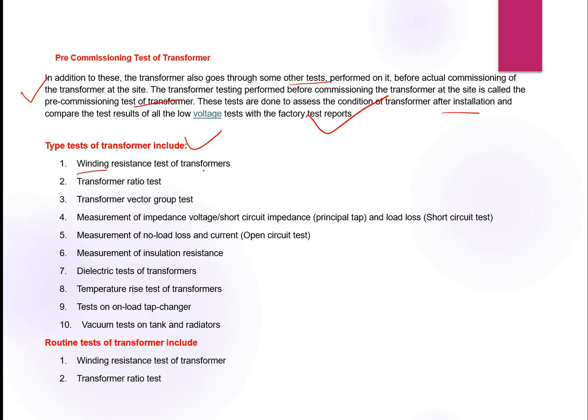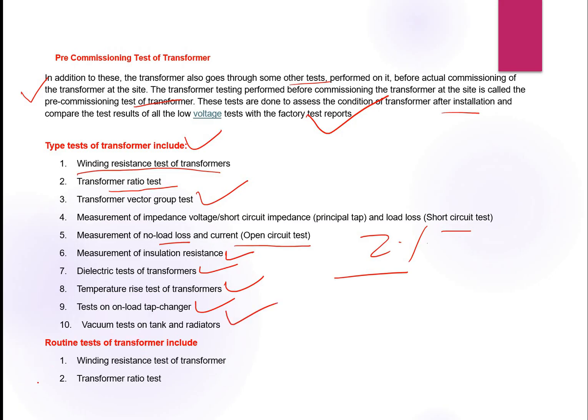Type tests are: winding resistance of the transformer, ratio test, transformer vector group test, measurement of impedance and short circuit impedance, meaning Z percentage at principal tap, short circuit test, measurement of no load loss and current (open circuit test), measurement of insulation resistance test, dielectric test of the transformer, temperature rise test of the transformer, test on the load tap changer of the transformer, and vacuum test on tank and radiators. This is the type test of the transformer.